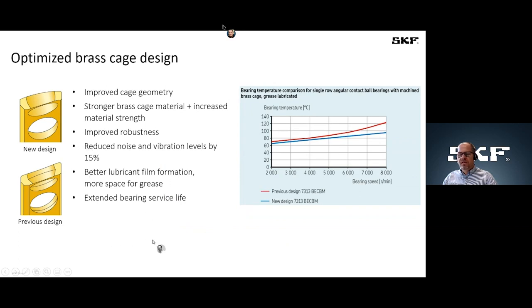What have we done on the cage? On the top you see the new design of the cage and on the bottom the previous design. And you can immediately see that we have improved the geometry itself. So this leads to better lubrication film formation between the ball and the cage itself. You have more space for the grease as this cross section is smaller of this new cage. And due to this better lubrication film formation, you have reduced temperatures, reduced noise and vibrations. On this graph you can see very nice the previous design in red and the lower temperature of the new bearings with the new brass cage. And all of these puzzle stones lead to an extended bearing service life at the end.